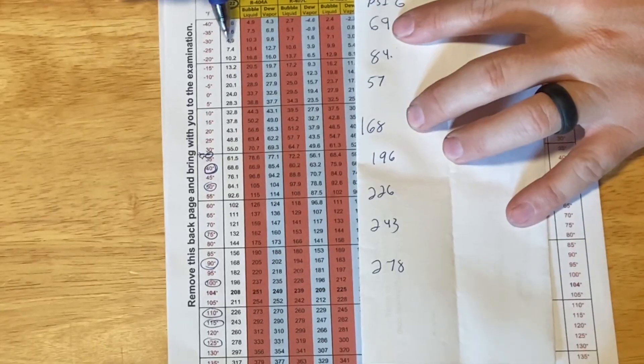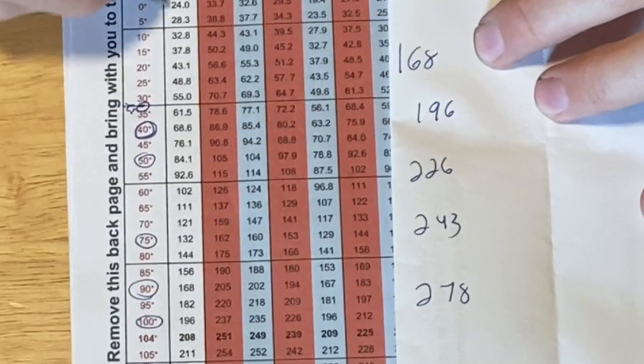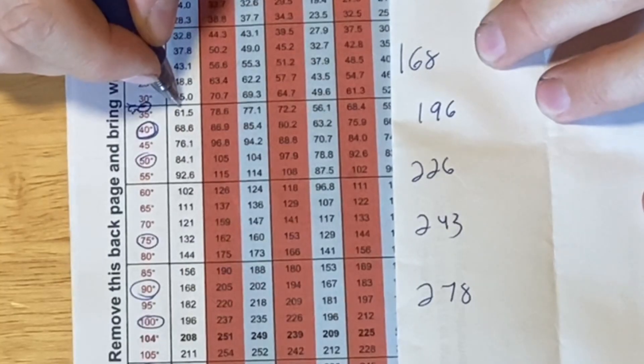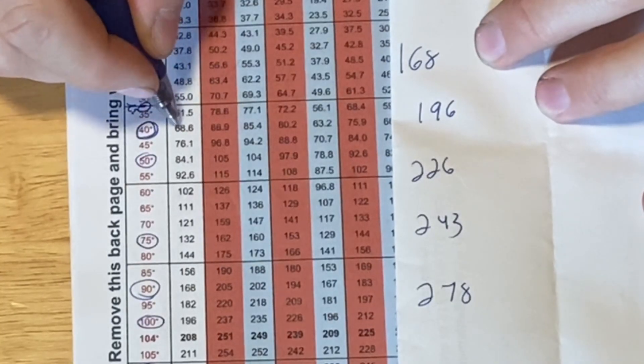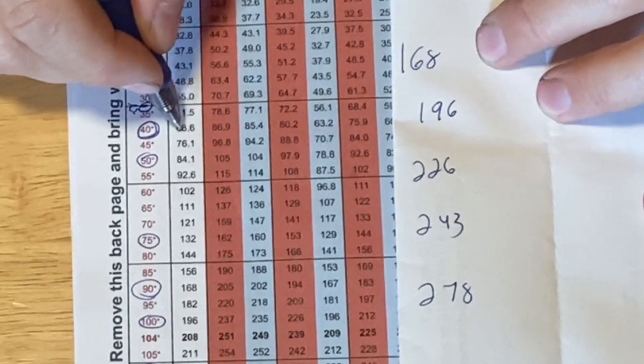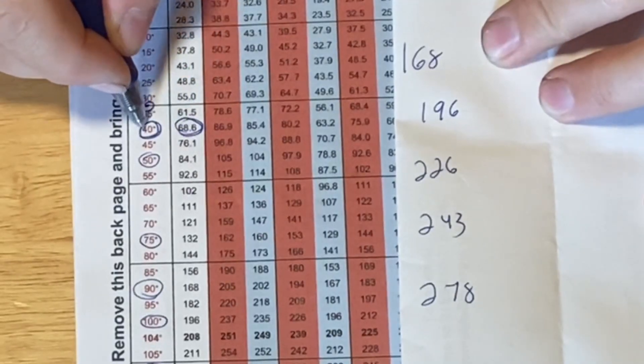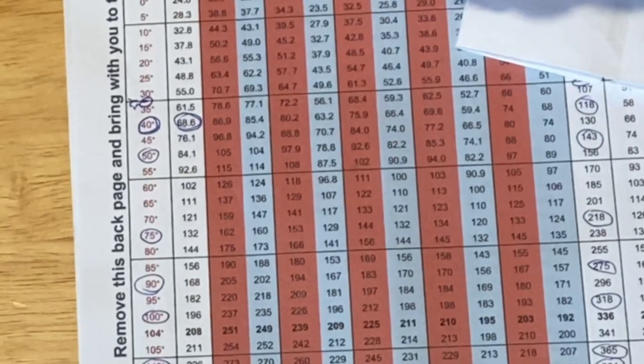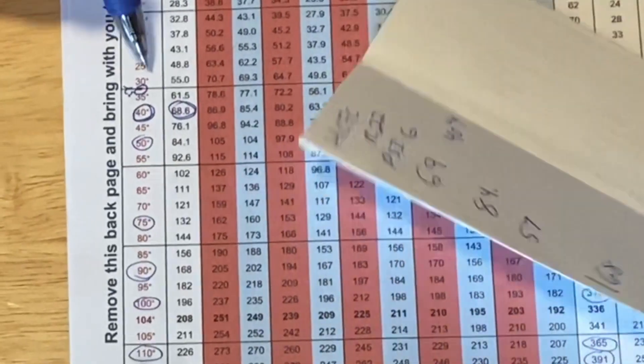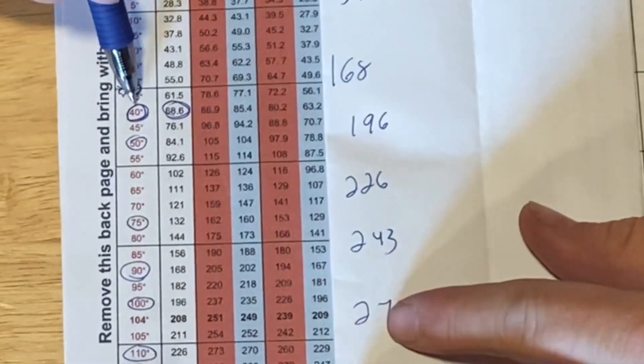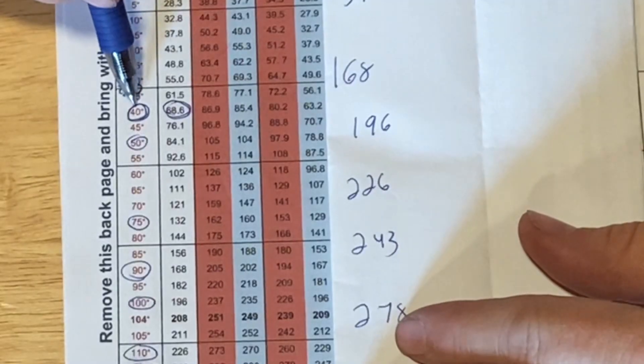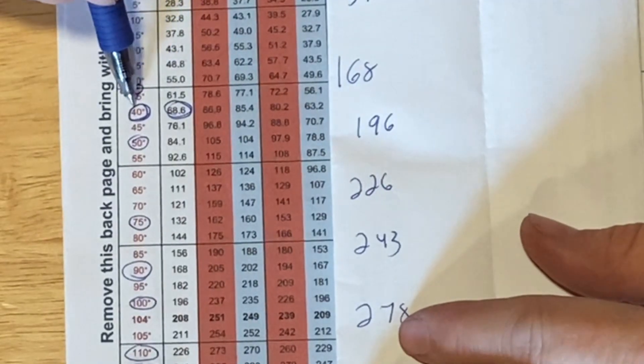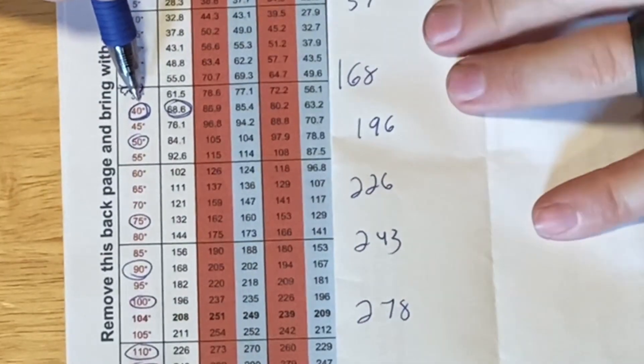All right here we go. So we're gonna start off with 69. So I'm gonna find over here R22. At 69 we're kind of right between these two numbers here. We get 68.6. That's pretty close. This is gonna be our pressure. And notice that converts to a saturated temperature of 40 degrees Fahrenheit. Notice before we already used 40. For 410A we had a different pressure but it also equaled 40.